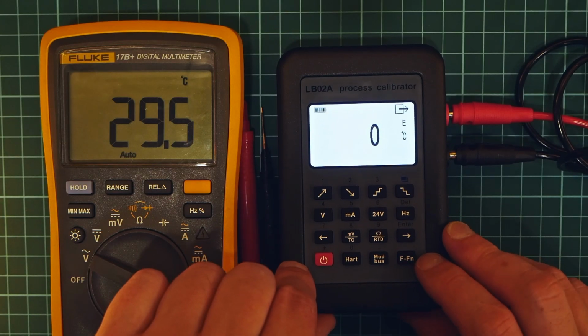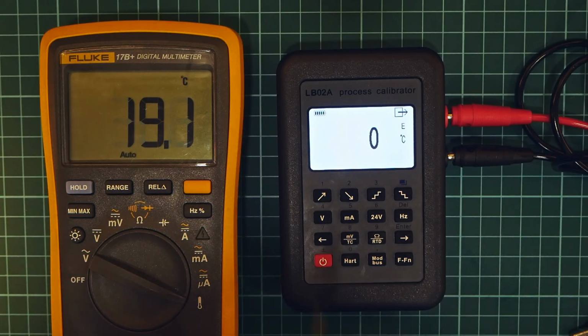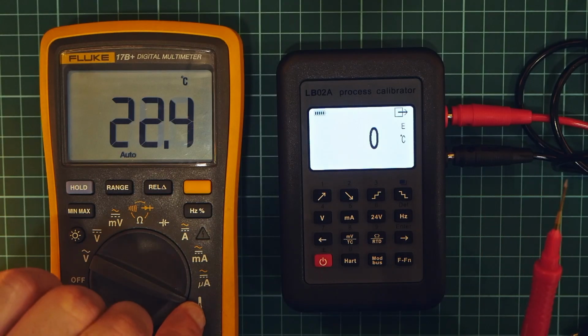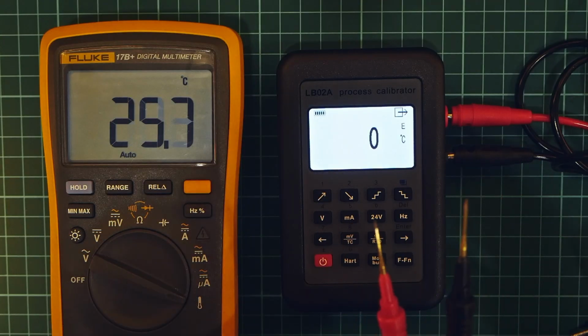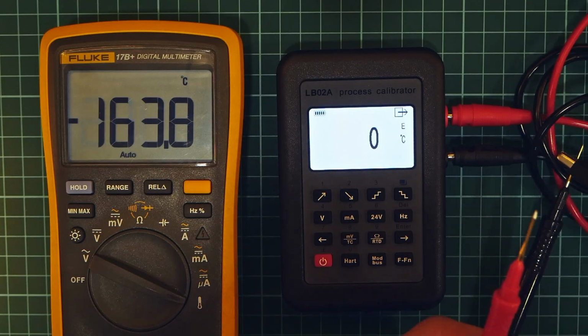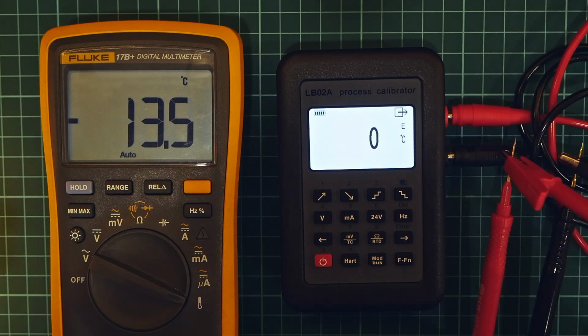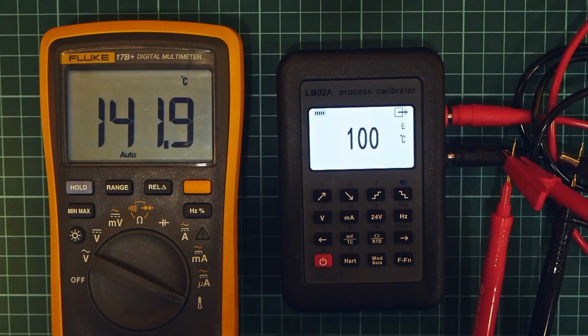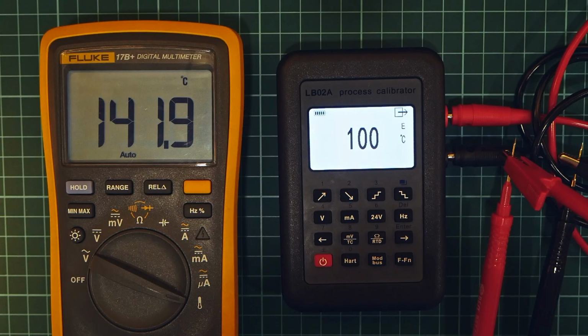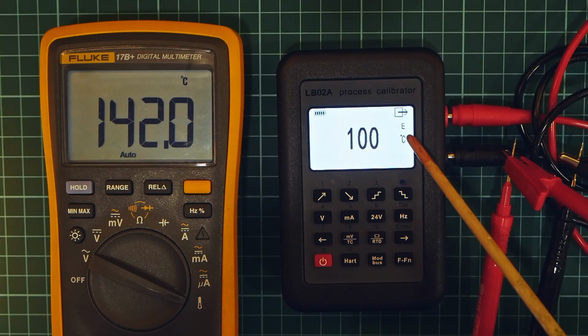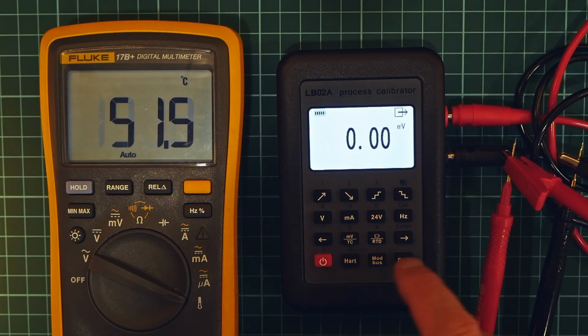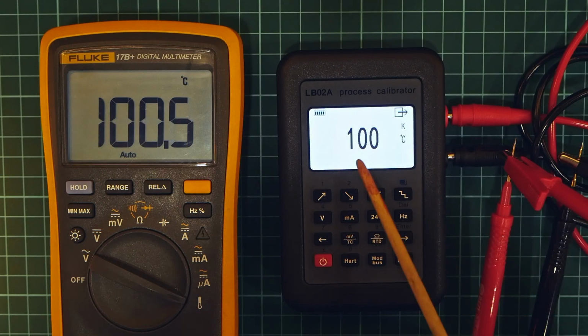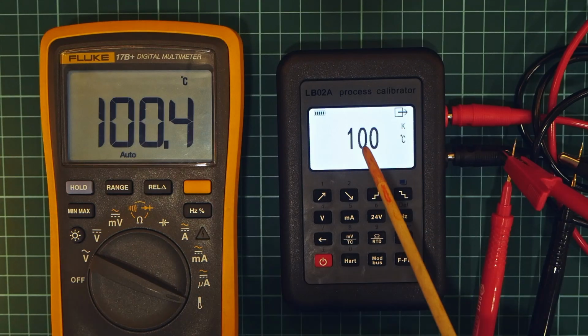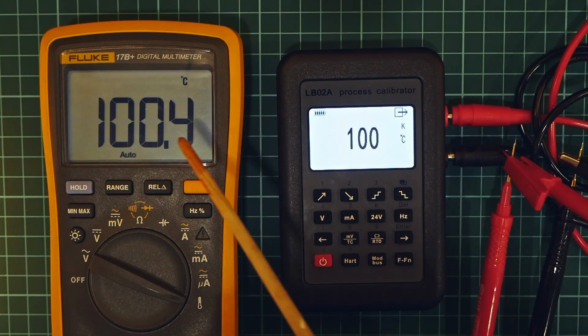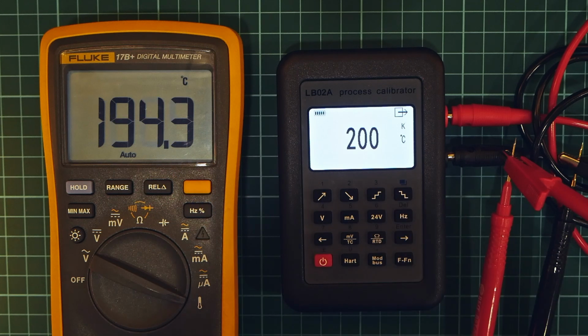And if we go to the main menu, so right now I'm in this multimeter thermocouple mode. I'm using just regular multimeter leads, and I connect them here. So imagine this is an analog input card, yes? We raise it to 100 degrees, so here is the problem, okay? It shows 100, but I selected the wrong thermocouple type. This supports K-type, so we need to find K-type, okay? So we are outputting from this device a 100 degrees Celsius signal. This shows 100.4.